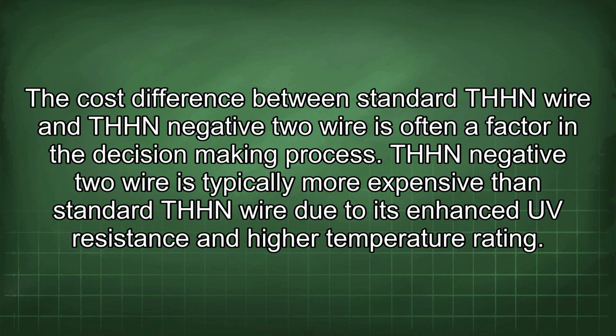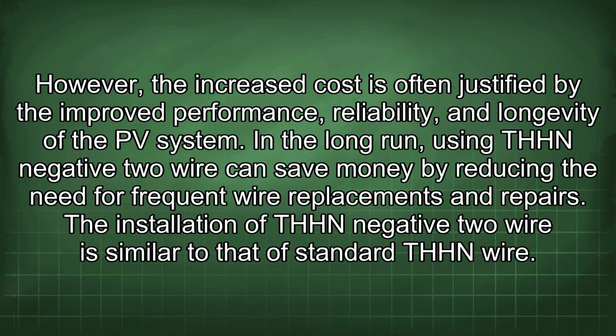The cost difference between standard THHN wire and THHN-2 wire is often a factor in the decision-making process. THHN-2 wire is typically more expensive than standard THHN wire due to its enhanced UV resistance and higher temperature rating. However, the increased cost is often justified by the improved performance, reliability, and longevity of the PV system. In the long run, using THHN-2 wire can save money by reducing the need for frequent wire replacements and repairs. The installation of THHN-2 wire is similar to that of standard THHN wire.